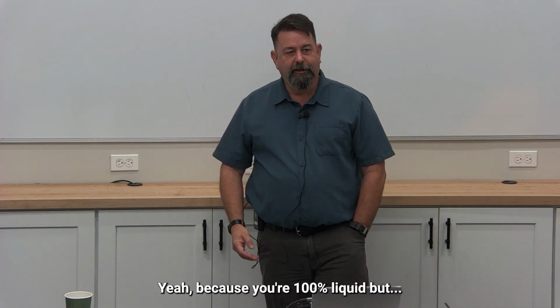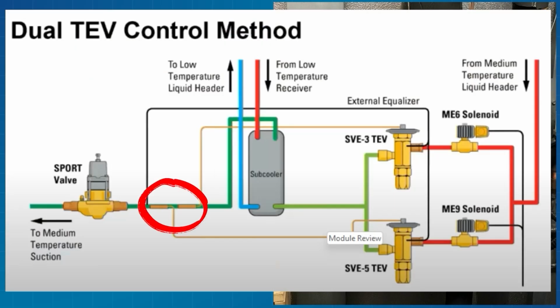Yeah, because you're 100% liquid. So, because I don't have any refrigeration effect, my superheat's a lie, right? And my line is actually warm, it's not cold, and my TXV, like I said, we'll talk about all that. So it's going to appear to me too as a technician, I'm going to screw my gauge on, put my temperature probe right here, and it's going to tell me I'm starving, and I'm going to want to open that valve. And it's already flooded. It's flooding so hard I can't even tell it's flooding until I look at my compressors.